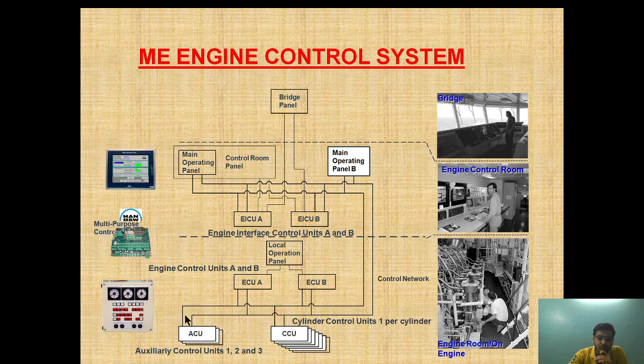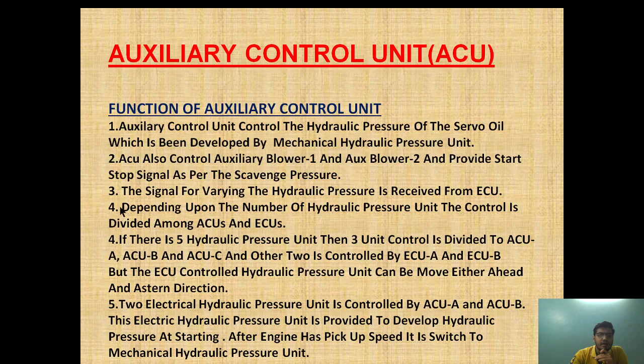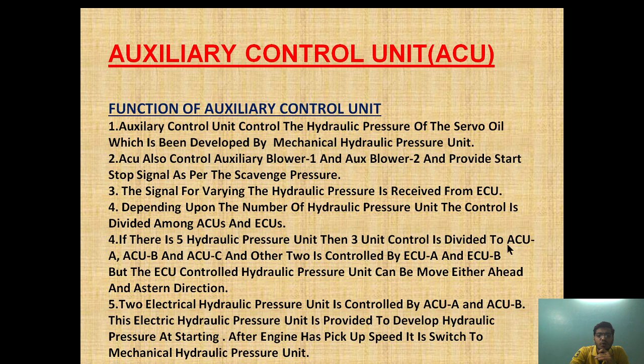If the speed is very slow ahead, the ECU will send a signal to the blower to cut in. When the speed is more than half — like full ahead — it will send a signal depending upon the scavenge pressure to cut off the blower. The signal for varying hydraulic pressure is received from the ECU. Depending upon the number of hydraulic pressure units, control is divided between ECU and ACU. Suppose there are five hydraulic pressure units: three units are given to ACU A, B, and C, and the other two are controlled by ECU A and B.